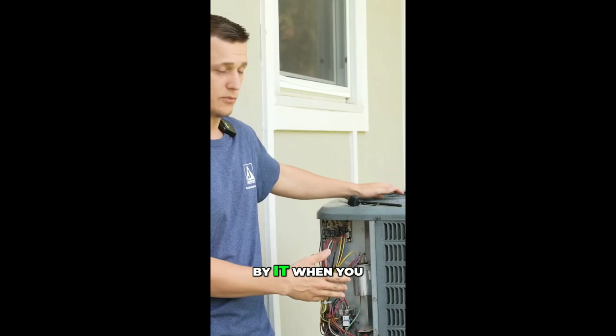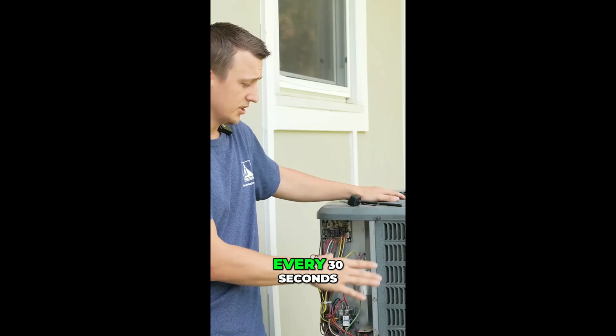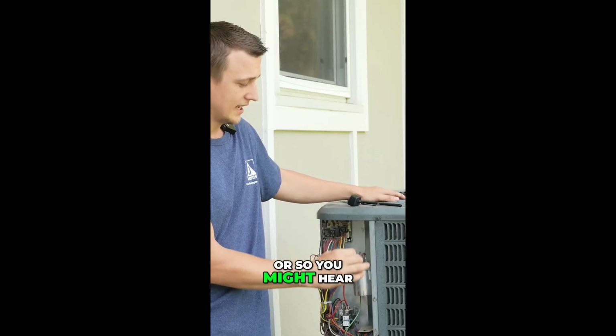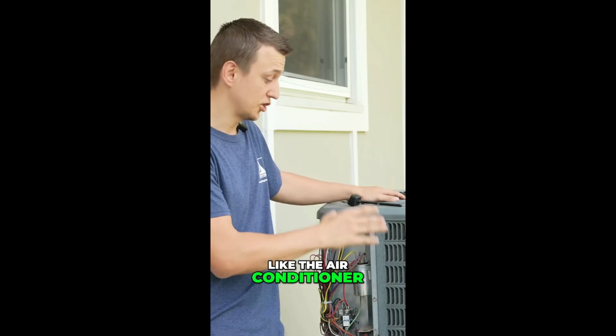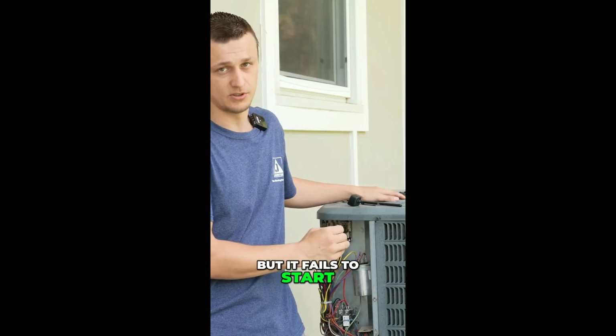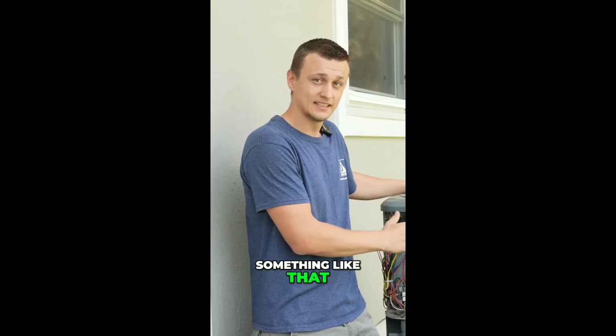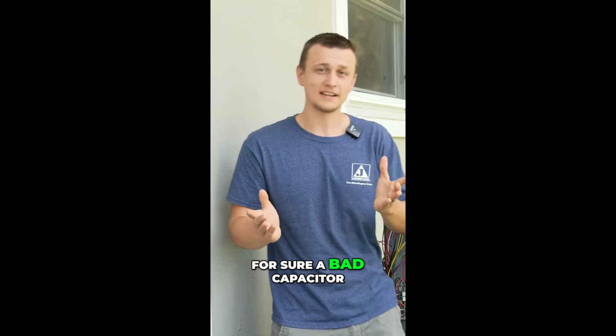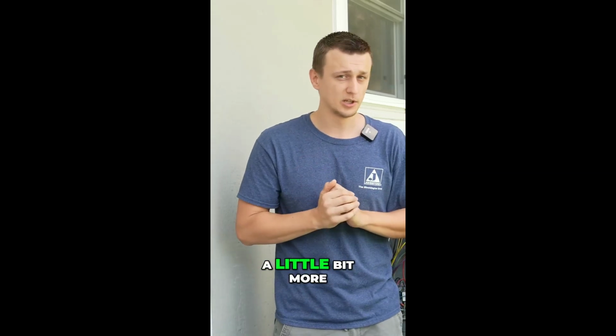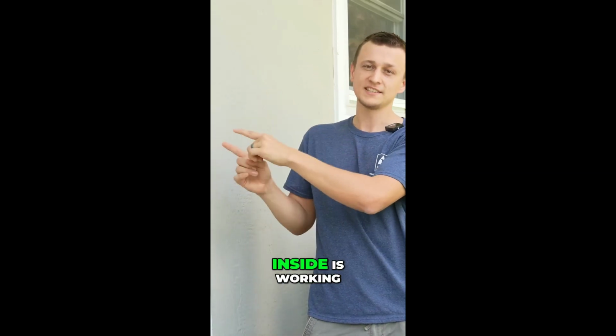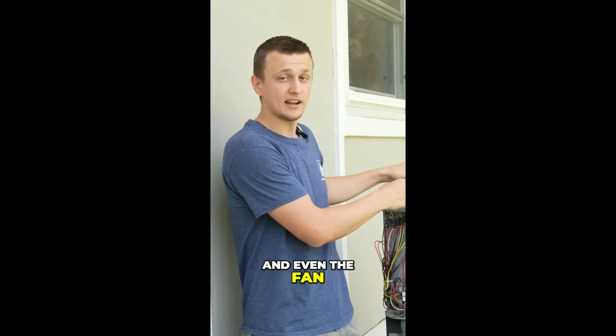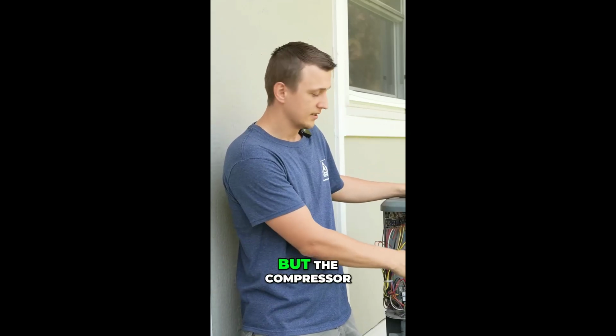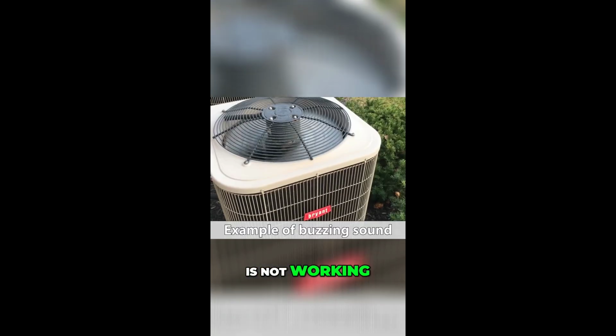And if you stand by it when you turn your AC on, every 30 seconds or so, you might hear a buzz, like the air conditioner is trying to start, but it fails to start. If you see something like that, that is almost for sure a bad capacitor. Another one, which is a little bit more tricky, is when the fan inside is working and even the fan outside is working, but the compressor is not working.